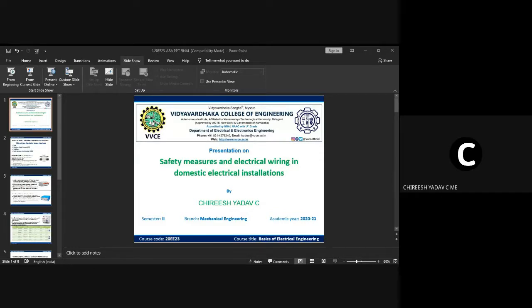Different types of earthing are pipe earthing, plate earthing, and strip earthing. The type of earthing used in our house is plate earthing. Location is near the meter board. In plate earthing, a copper plate or galvanized plate is buried in an earth pit below ground level. The plate electrode connects the electrical conductors to the earth.